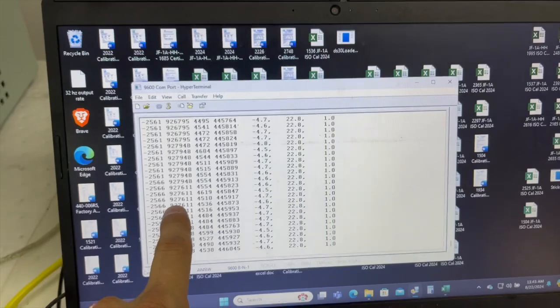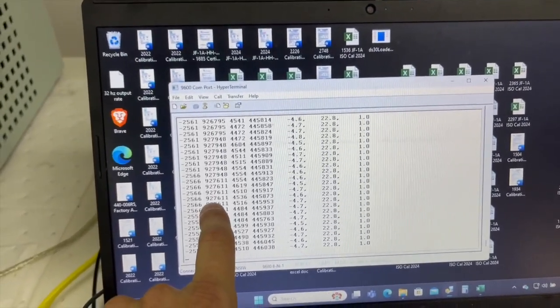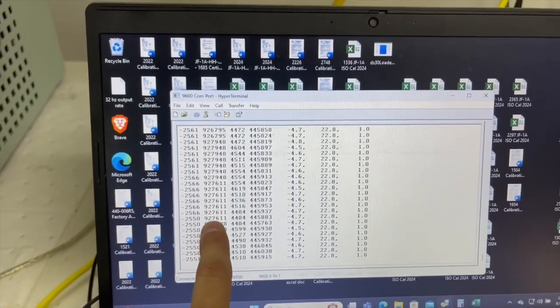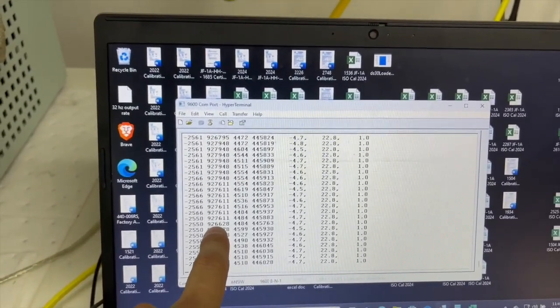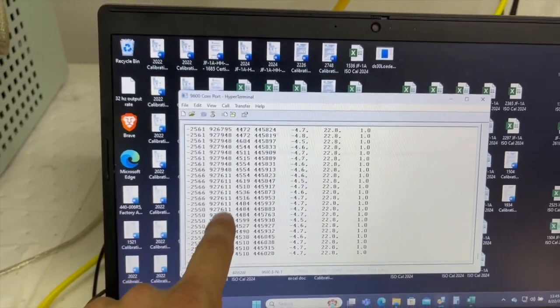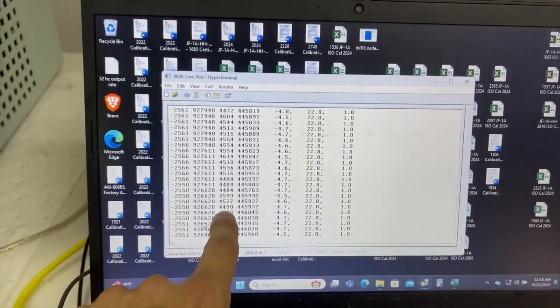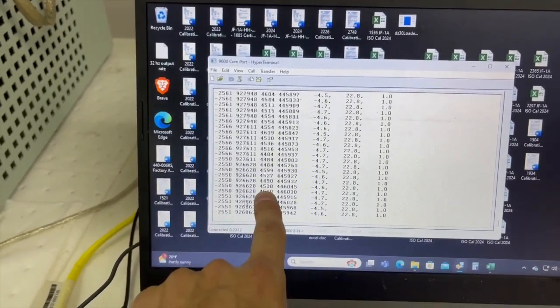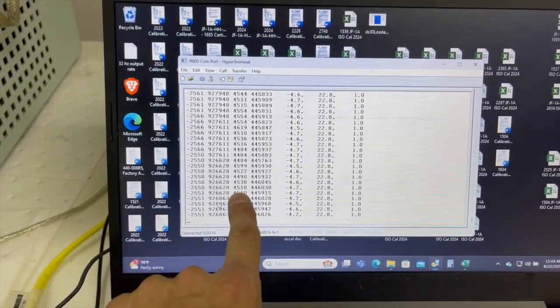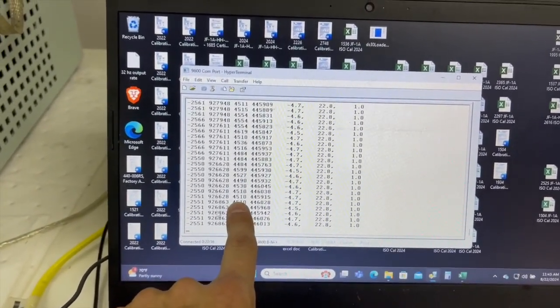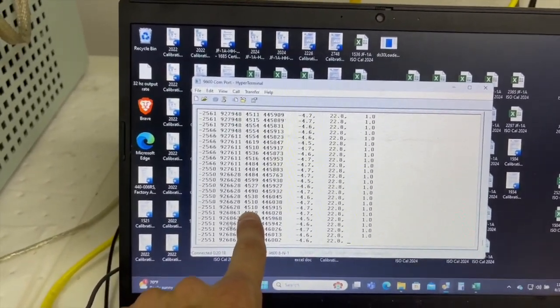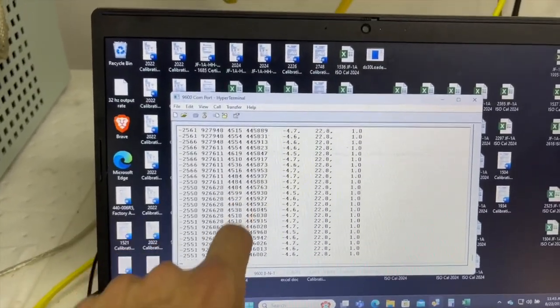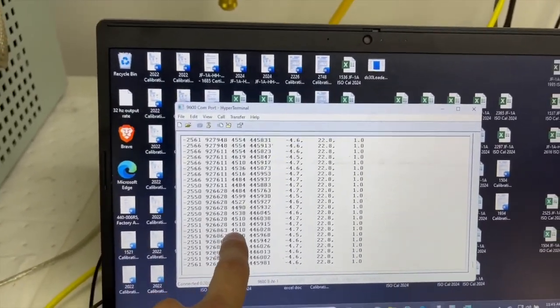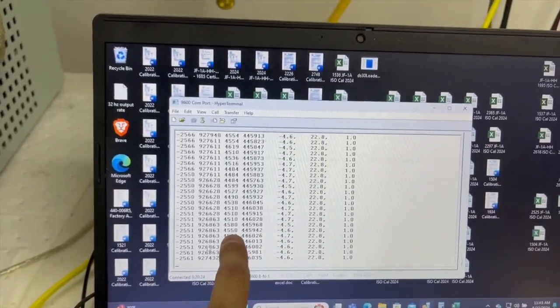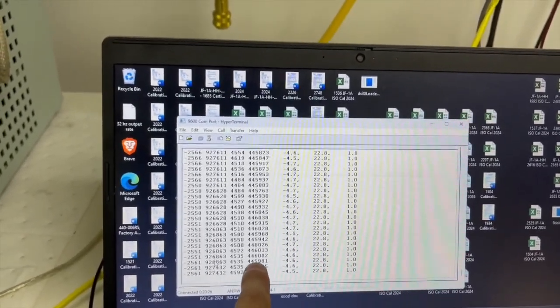You can move on. This is your full scale counts. Those should be somewhere between 600,000 and 1 million. So you can see here, that's good. This right here is your sensor counts. Those should be between minus 15,000 and 15,000. That's your conductivity. So somewhere in between those two numbers right now, 4,000 is fine.